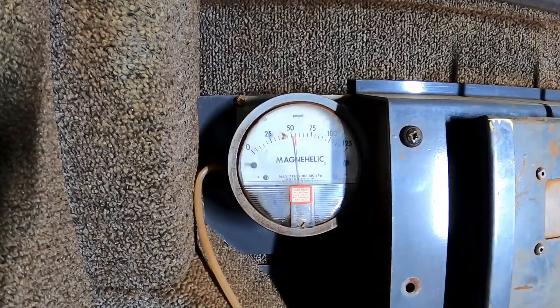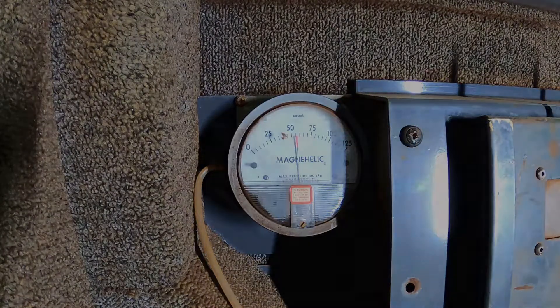Just behind me in the cab we have a Magnehelic gauge and this gauge is going to tell us how much pressure we have in the cab. Let's power it up and have a look. We've got 50, or just a bit over 50 pascals of pressure in there. On any site across Australia this machine would go to work because that's acceptable cab pressure — it's probably considered quite good.